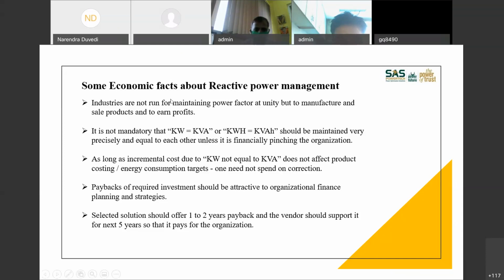So it is not mandatory that kW equal to kVA or kWh equal to kVAh should be maintained very precisely and equal to each other, unless it is financially pinching to the organization. As long as the incremental cost due to kW not equal to kVA does not affect product costing or energy consumption targets, one need not spend on correction. Energy consumption targets are added because we have a lot of multinationals working in India.